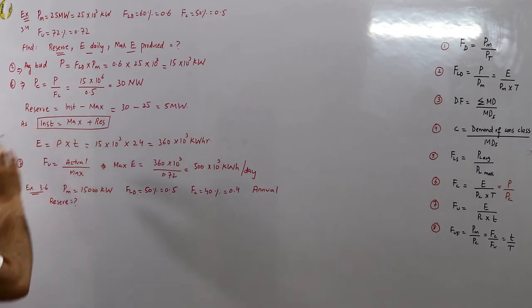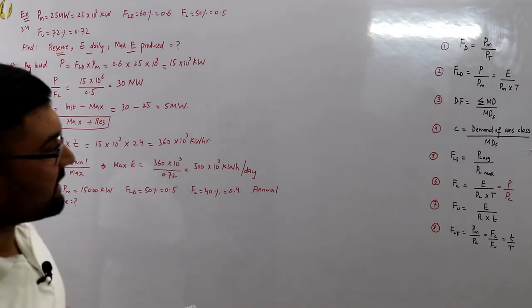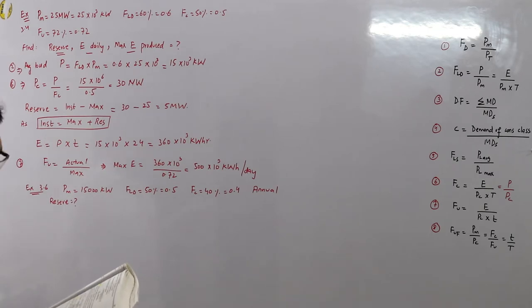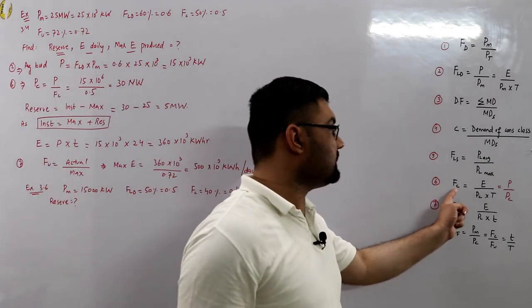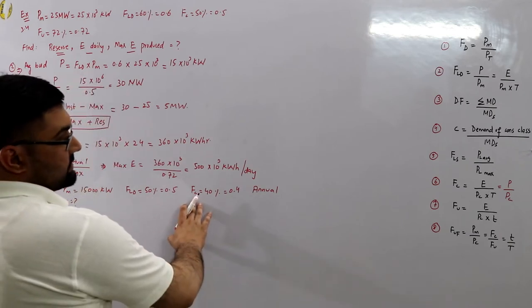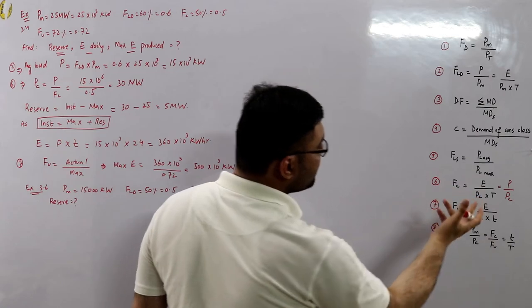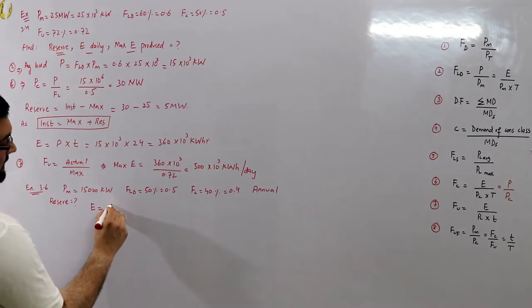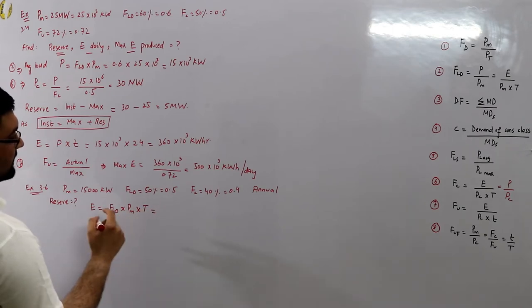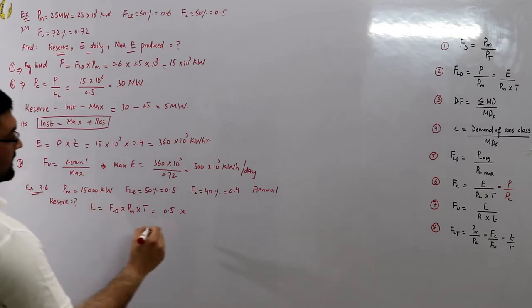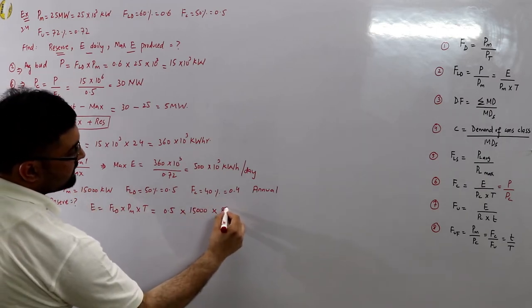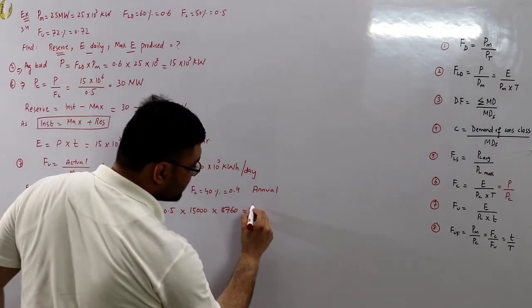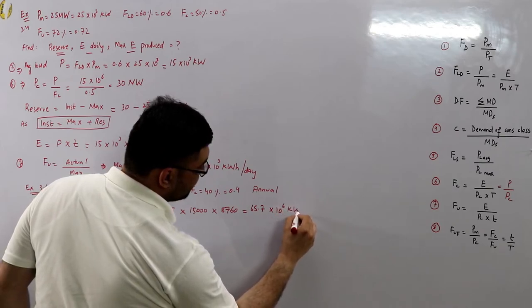The installed capacity can be found from the capacity factor. For the formula, we need energy E, which we find from the load factor: E = FLD × maximum demand × time = 0.5 × 15,000 × 8,760 hours = 65.7×10⁶ kilowatt-hours per annum. Now we can calculate installed capacity PC.